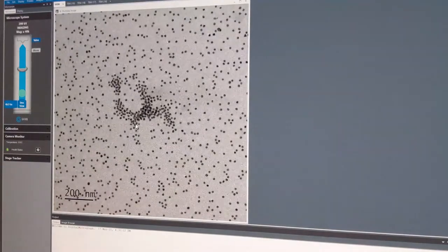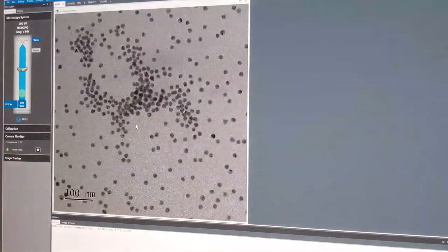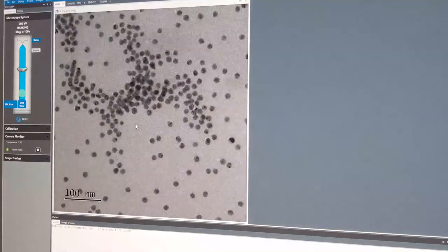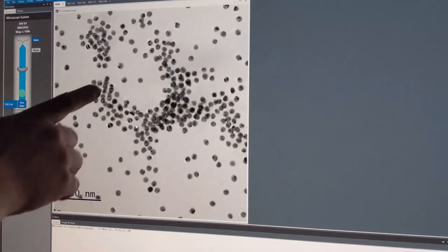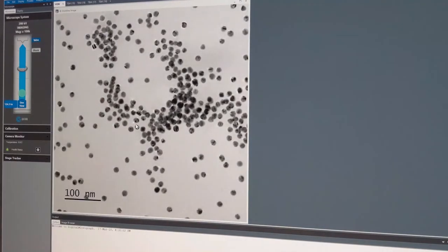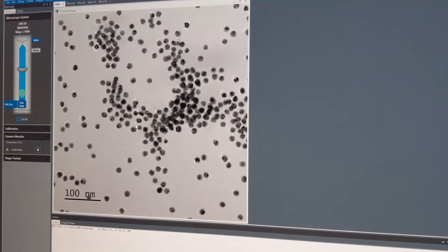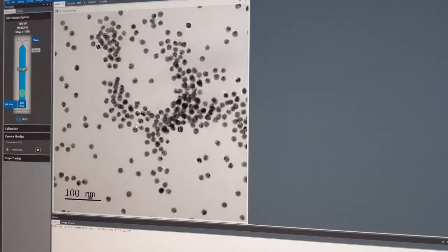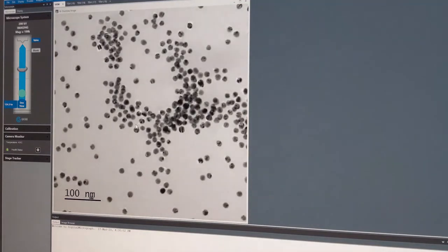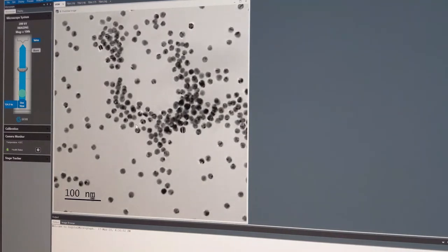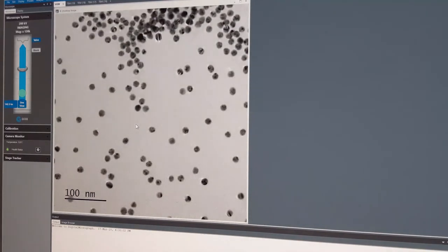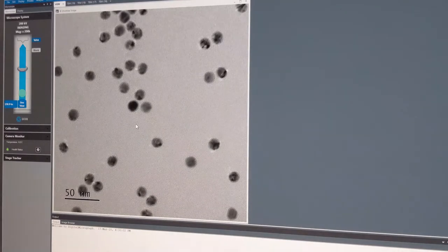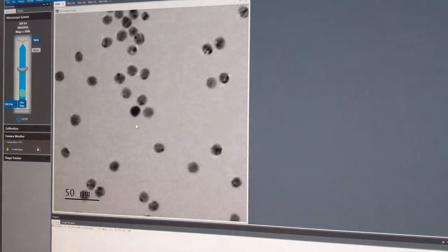If I magnify further to about 100,000 times and just increase the brightness to make it more visible, we can see, for example, here we have a string of nanoparticles. And they're all touching each other and slightly overlapping. What this means is we can't accurately see the edges, which we need to be able to do to measure their size. So we don't use regions like this for size determination.